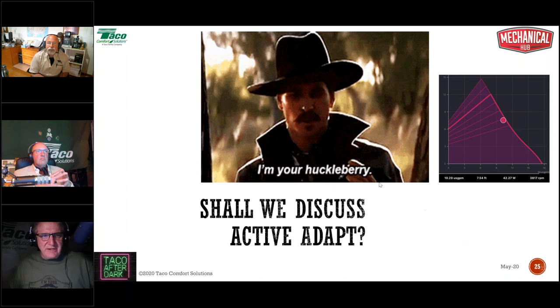Good stuff. Plenty of stuff coming in now, question-wise. So what do we got? How accurate is the GPM head loss of the app output? In past designs, I've found this to be inaccurate without delta P feedback. That's from Darren. We're claiming that as long as you're in the sweet spot, we're within about 5%, which is as good as any balancing valve or anything else out there. Again, if you're way up to the left or way out to the right, the accuracy goes down.